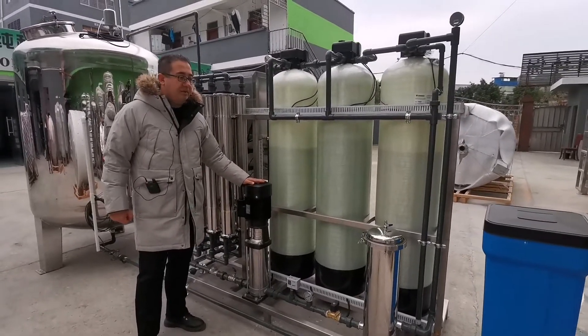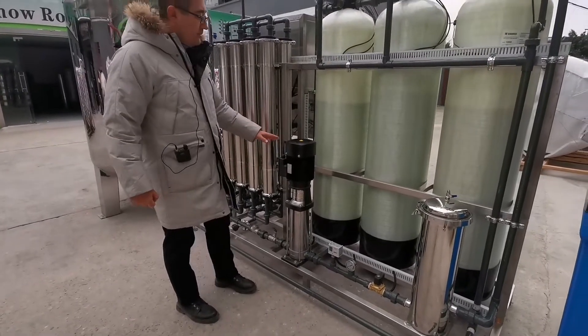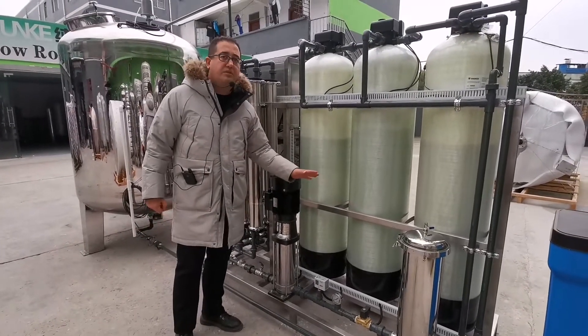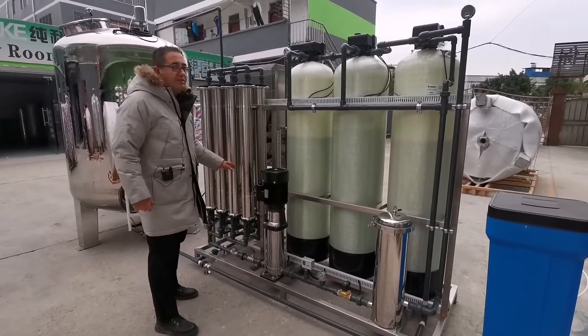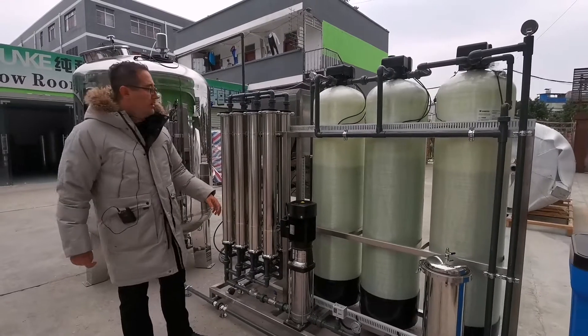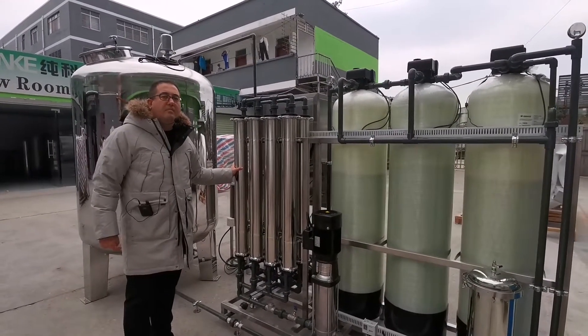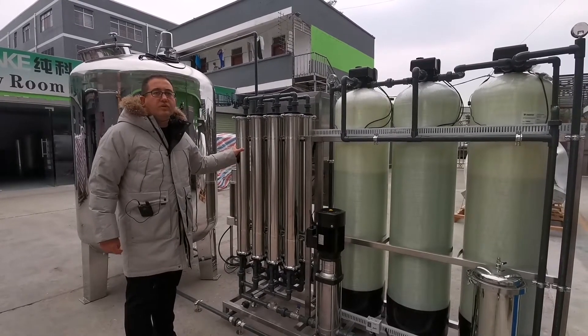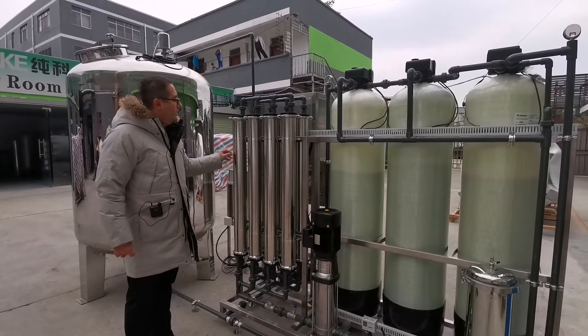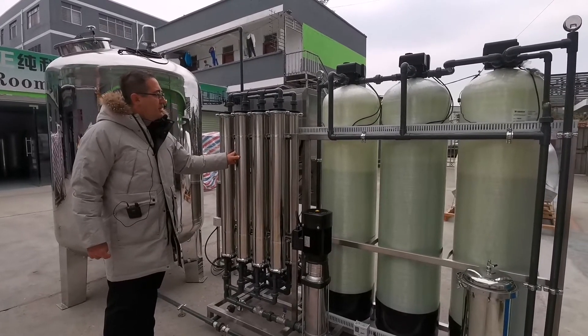The high pressure pump pumps the raw water to the membrane. Before the high pressure pump, our design pressure is about 3 bar, and after the high pressure pump it is 10 bar. In this project, as you can see, we are using a stainless steel membrane housing. We use Vontron brand 4040 membranes, with eight pieces in total.